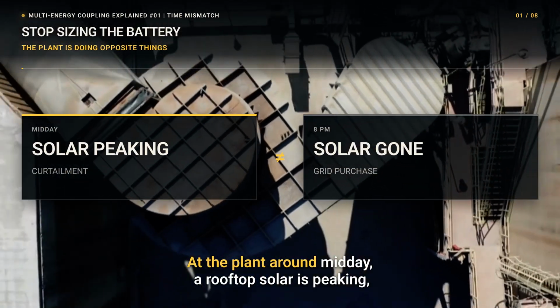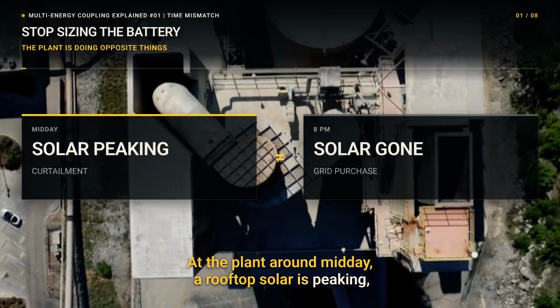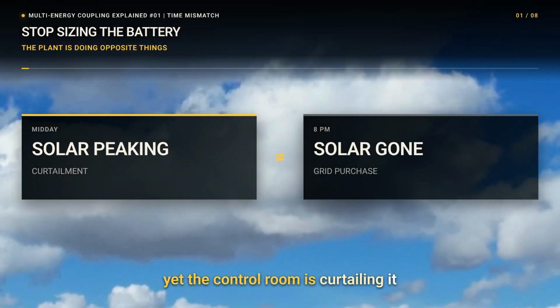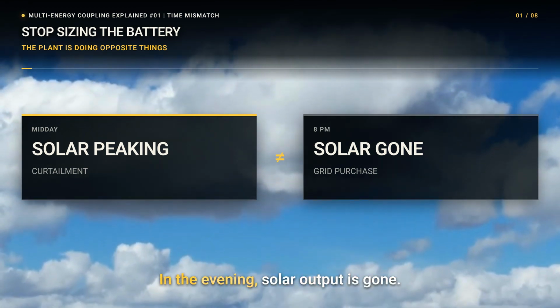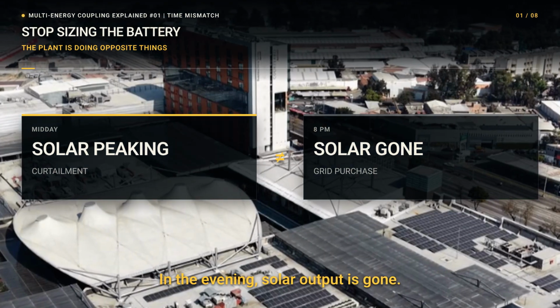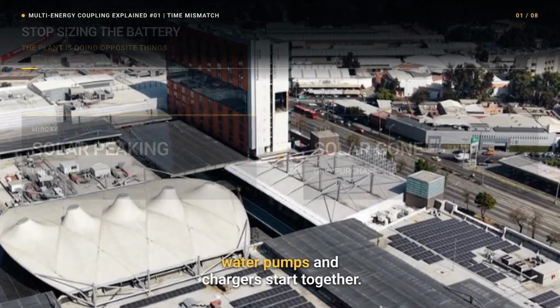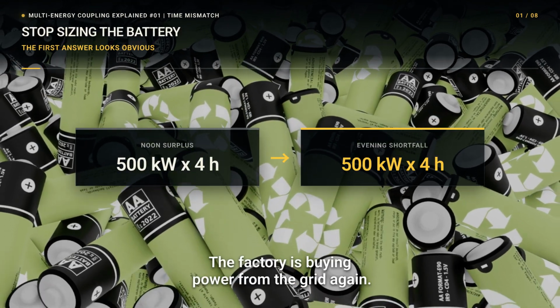At the plant around midday, a rooftop solar is peaking, yet the control room is curtailing it. By 8 in the evening, solar output is gone. A chiller plant, water pumps, and chargers start together. The factory is buying power from the grid again.